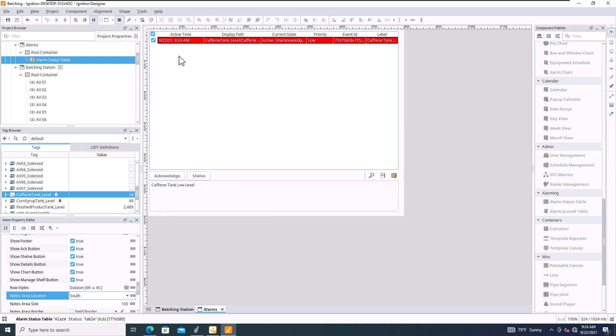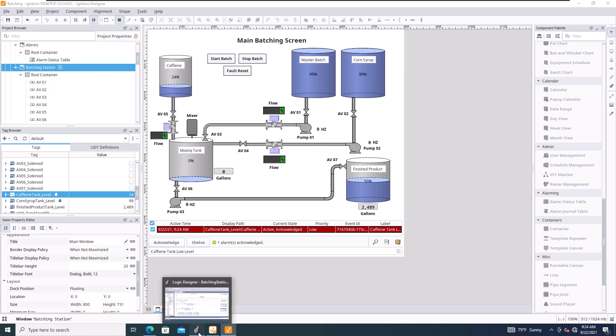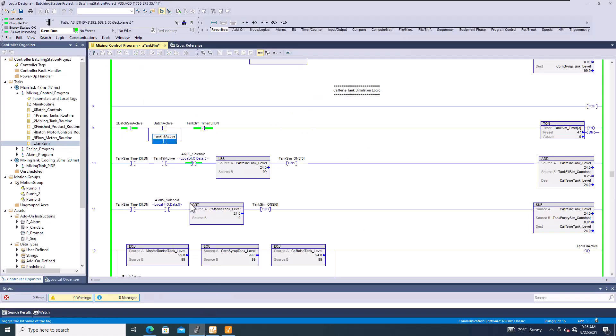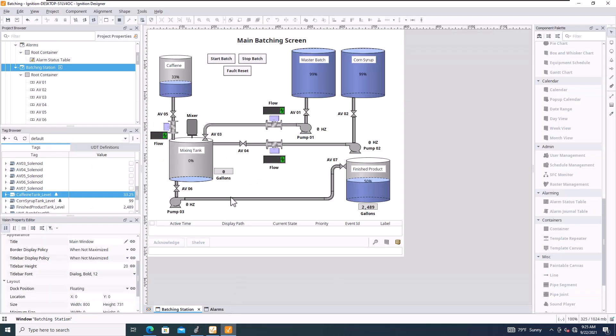On the alarm screen you can see the notes — click the alarm and it shows 'Caffeine Tank Low Level.' Same thing for the batching alarm. You can acknowledge an alarm, but it won't go away until the underlying problem is resolved. Once I fill the tank back above 25 and it was already acknowledged, it automatically disappears.